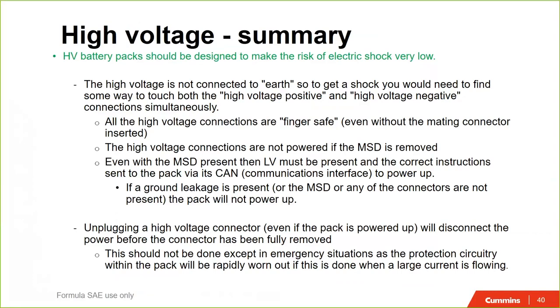If you have a touch-proof connection, a high voltage connection, even with the pack powered up, it is possible to disconnect it. The automotive connectors have the HVIL loop in them, and if we disturb that, it's a two-stage pull-out. It is a way to remove power. You really shouldn't do that, except in emergency situations, because it creates an arc across the face of the contactors, and your contactors then become unreliable.